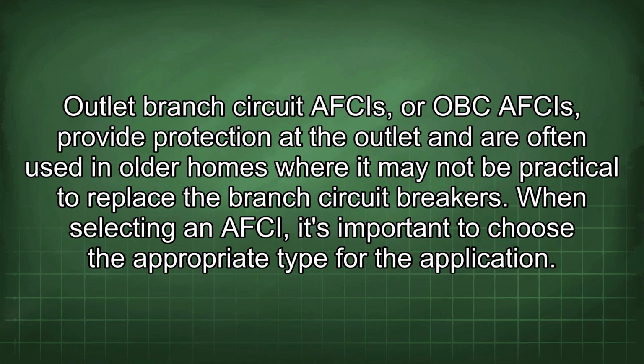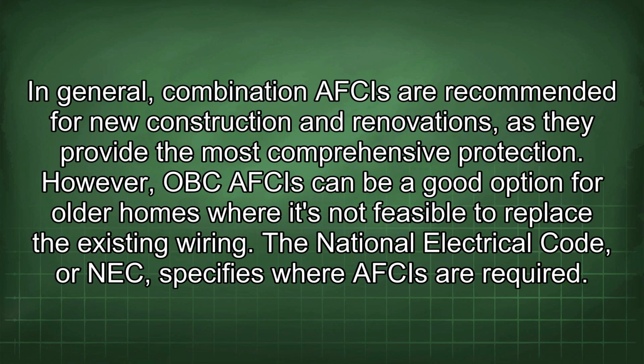Outlet branch circuit AFCIs, or OBC AFCIs, provide protection at the outlet and are often used in older homes where it may not be practical to replace the branch circuit breakers. When selecting an AFCI, it's important to choose the appropriate type for the application. In general, combination AFCIs are recommended for new construction and renovations, as they provide the most comprehensive protection. However, OBC AFCIs can be a good option for older homes where it's not feasible to replace the existing wiring.